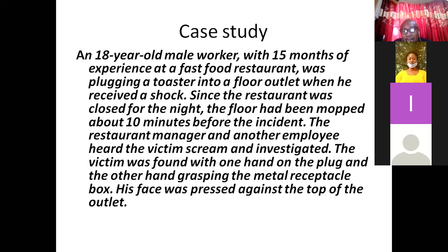The restaurant manager and other employees heard the victim scream and investigated. The victim was found with one hand on the plug and the other hand grasping the metal receptacle box. His face was pressed against the top of the outlet.